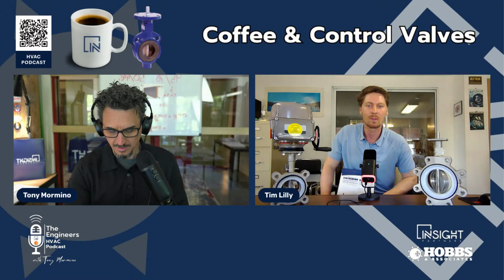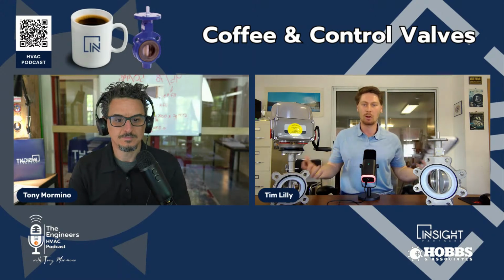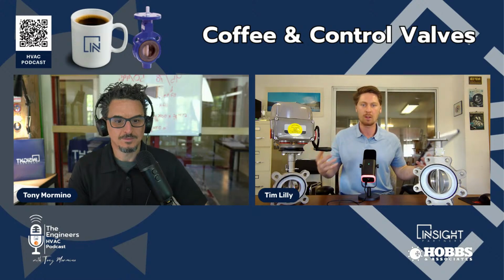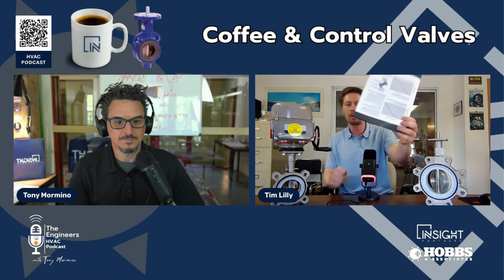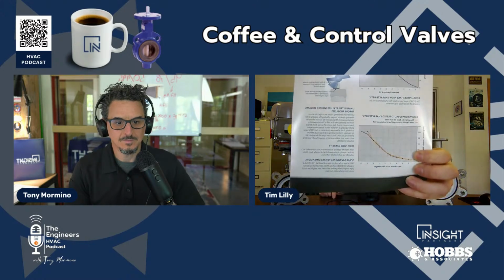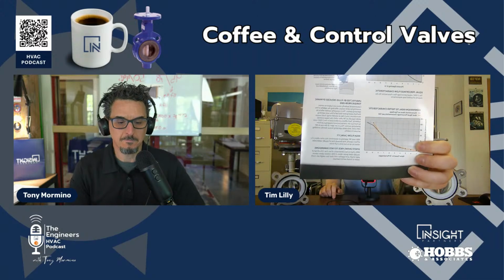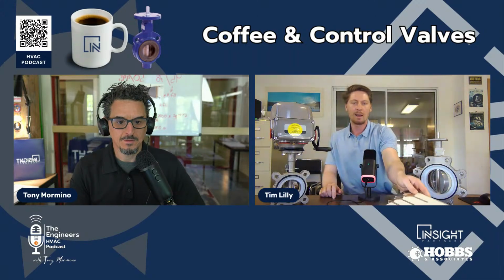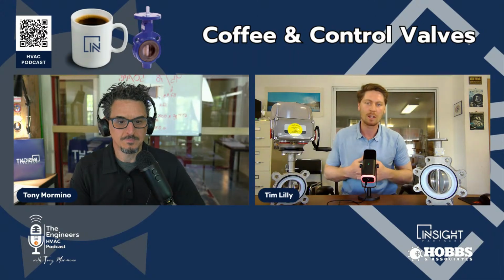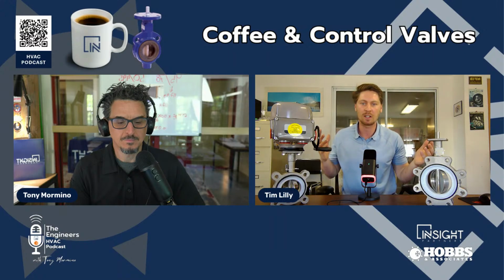Great, okay. And so when you pay for a control valve, you're paying for what's called equal percent flow characteristics, which hopefully you can see it right there - that parabolic looking line. And basically what that means is for every 5% change in your disk, you get a 5% change in your flow.